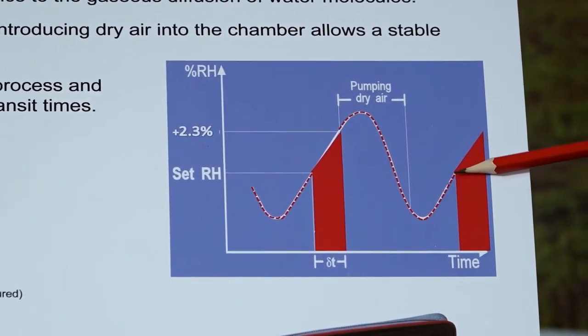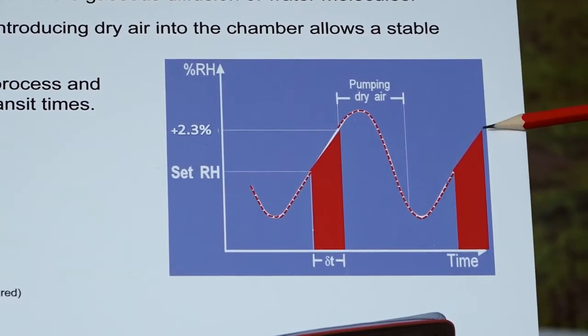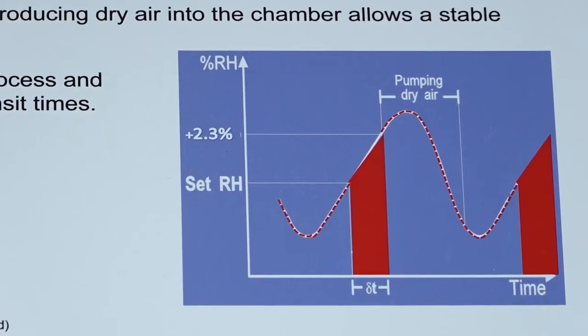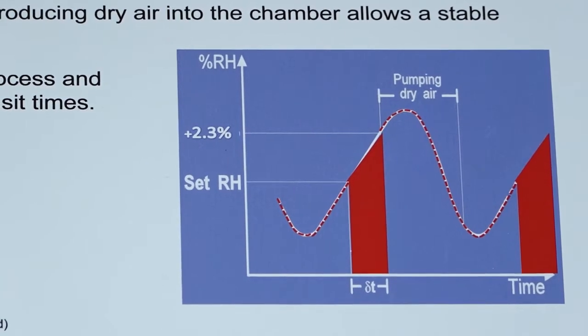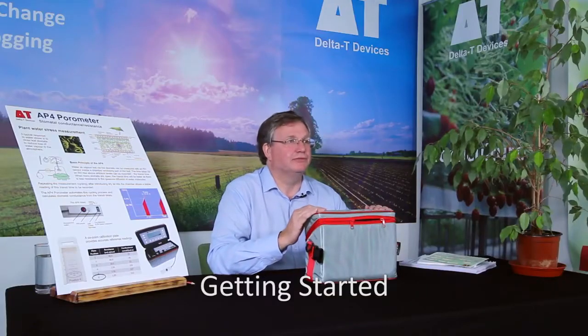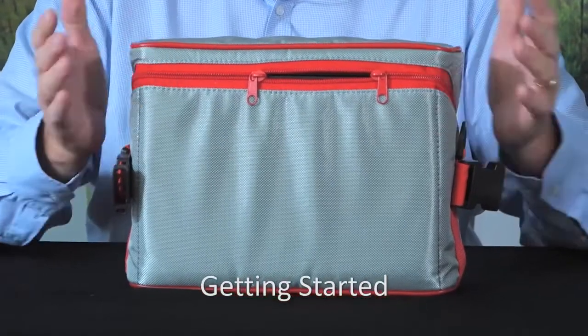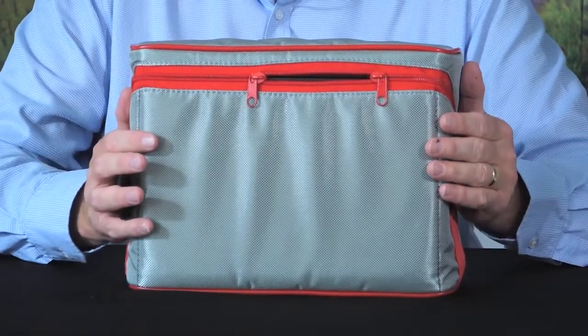And it will keep cycling through this until 2 stable readings are achieved. And you can set the AP4 so that when 2 stable readings are achieved that are within 2% of each other, there's an audible double beep, and you know you've reached a stable measurement and you can store it. So let's have a look at the AP4. It comes in a carrying case with straps and a shoulder strap for carrying it around the field.